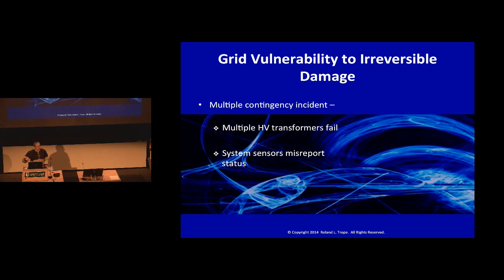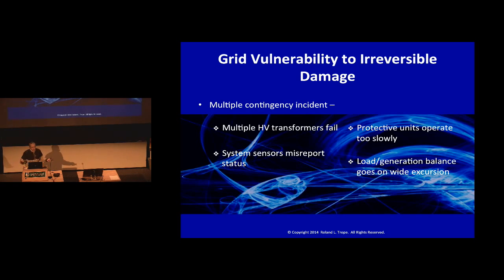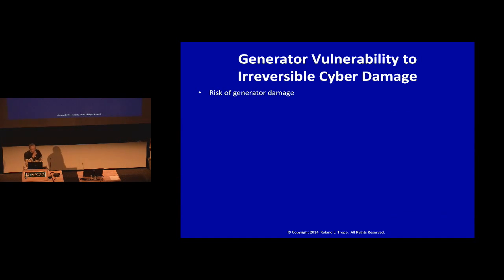In other words, they start misbelieving the part that's accurate and believing the part that's false. The protective units might then operate too slowly. You get a load generation imbalance, goes on a wide excursion, and the cascading effect begins, cascading outages. There would be, in the case of that kind of an attack, a risk of generator damage. And remember that any mechanical failure in the generator is potentially volatile, highly dangerous. You could easily have an explosion.